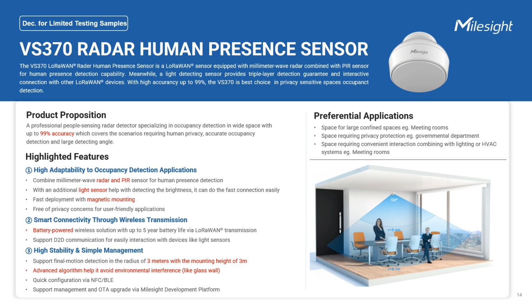So the correct answer is that PIR will not be affected, but radar might be influenced by dynamic objects outside the glass. But don't worry, you can resolve this issue through proper installation. Just look at the picture. When the device is mounted on a ceiling, 3 meters high with a 120-degree field of view, it can accurately pick up slight human movements like typing on a keyboard or writing, within a 3 to 4 meter radius detecting range. If the range is extended to 6 or 7 meters, it can detect normal human movements.